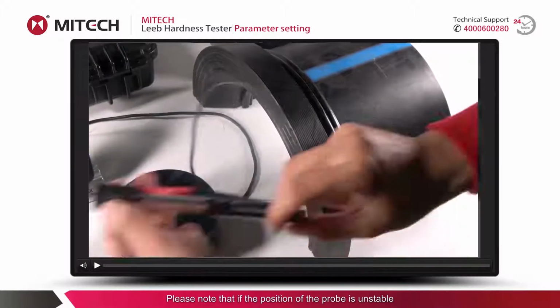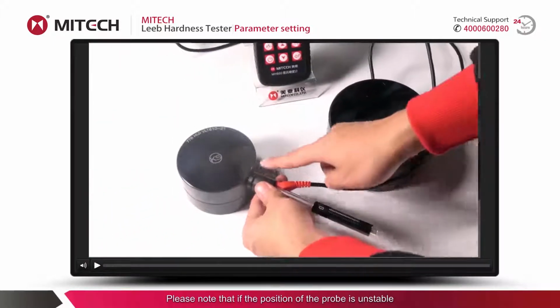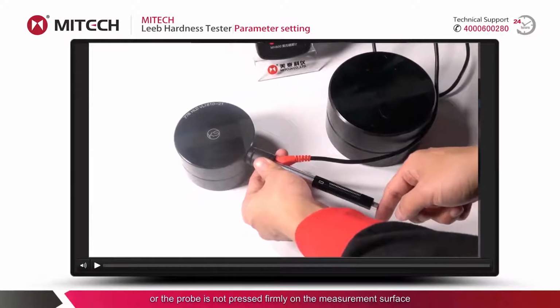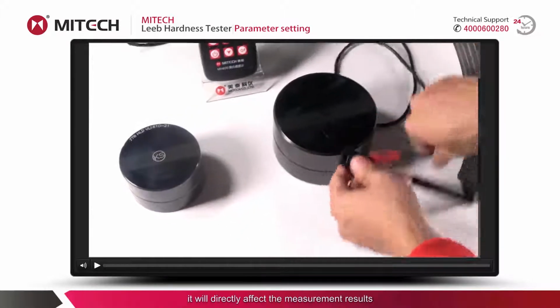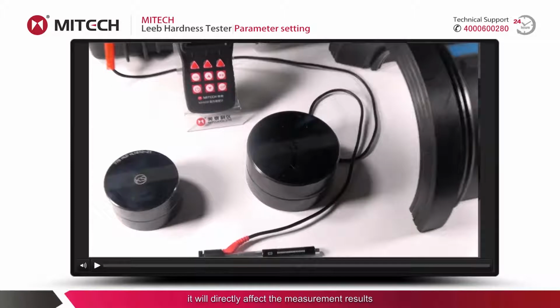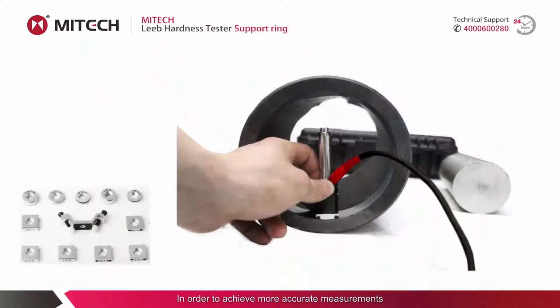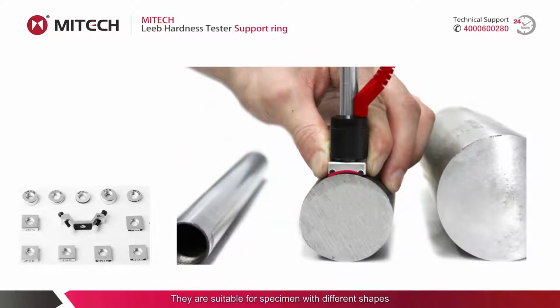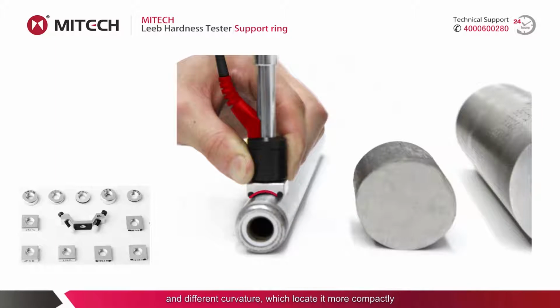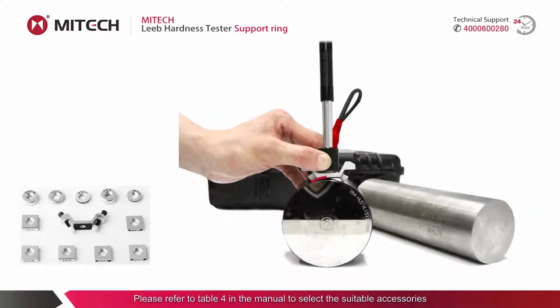Please note that if the position of the probe is unstable or the probe is not pressed firmly on the measurement surface, it will directly affect the measurement results. In order to achieve more accurate measurements, Mitech has 12 types of special support rings for selection. They are suitable for specimens with different shapes and different curvature, which are located more compactly. Please refer to Table 4 in the manual to select the suitable accessories after positioning correctly.